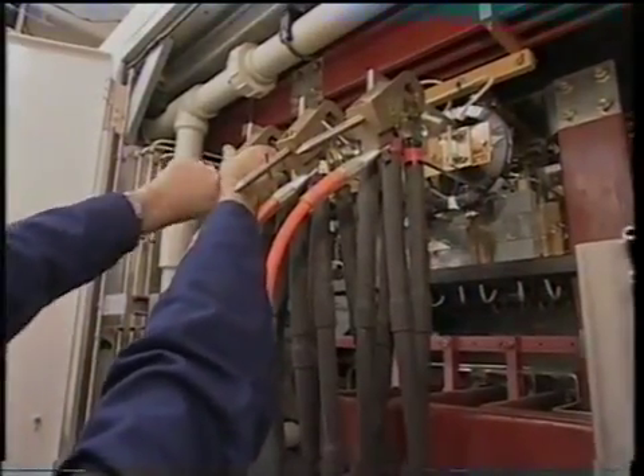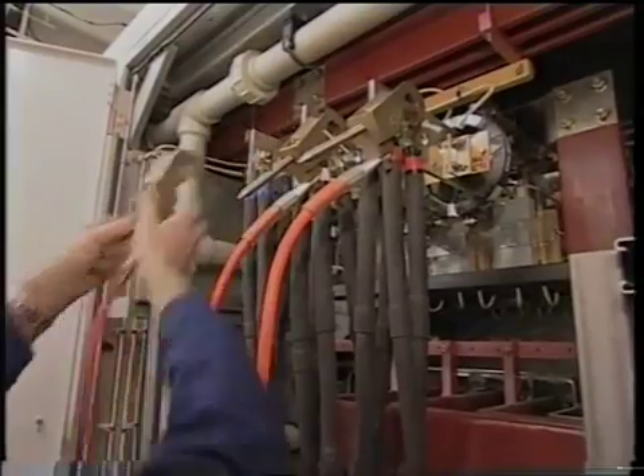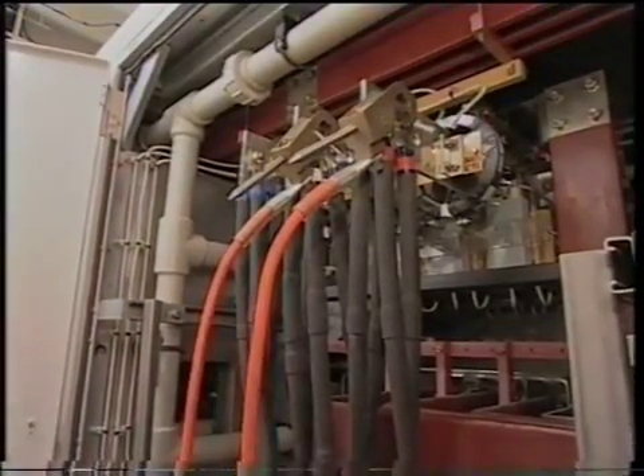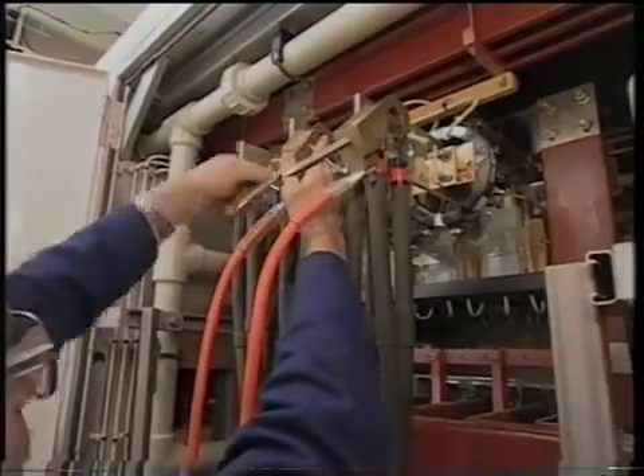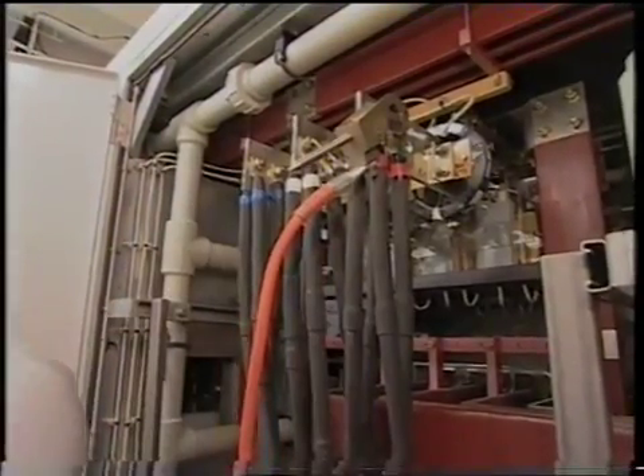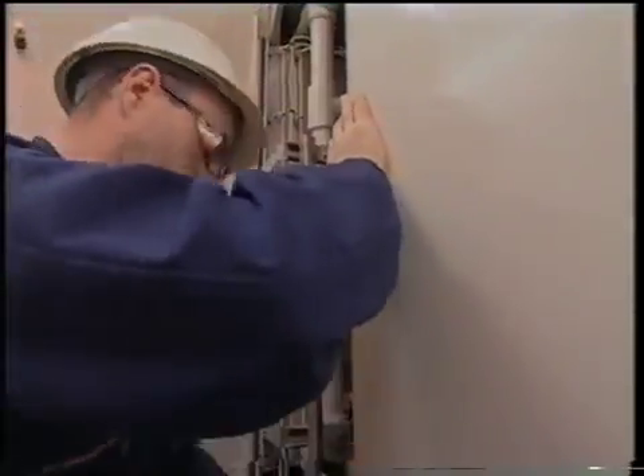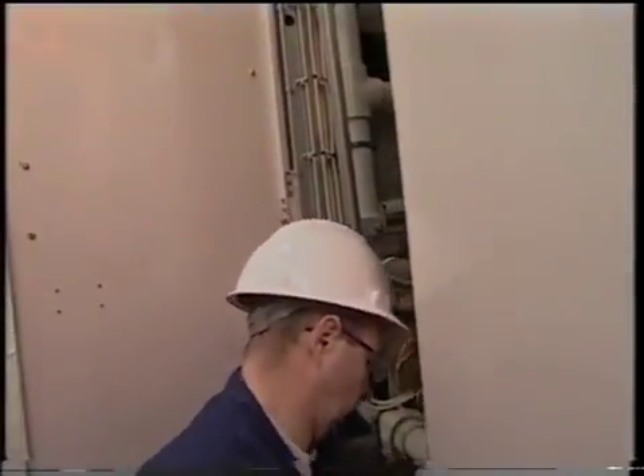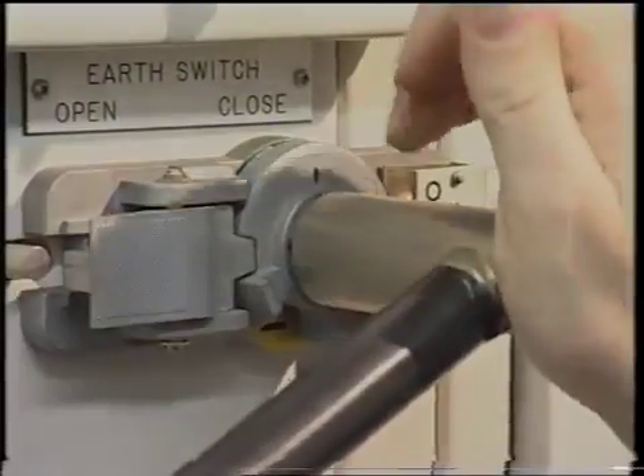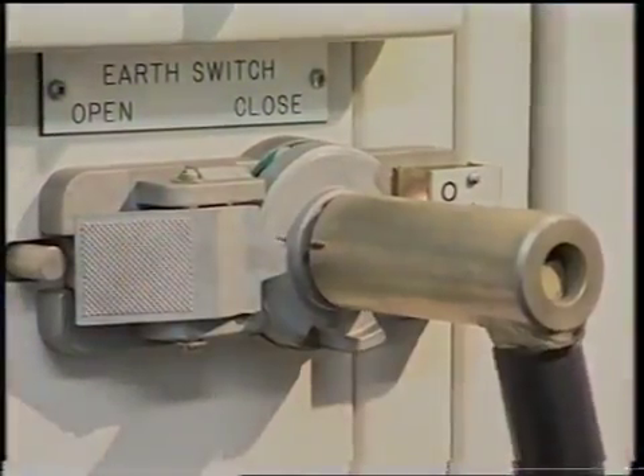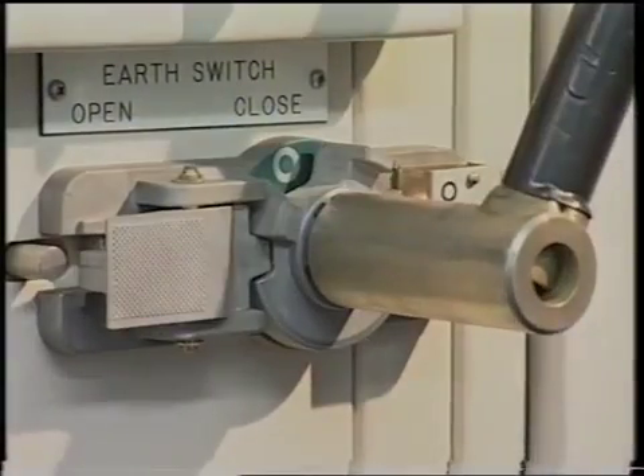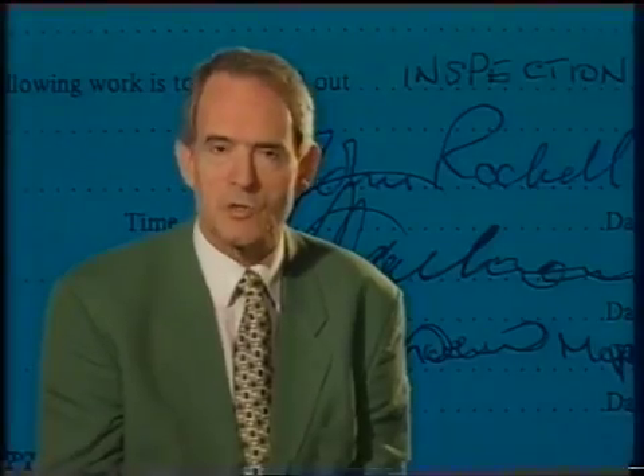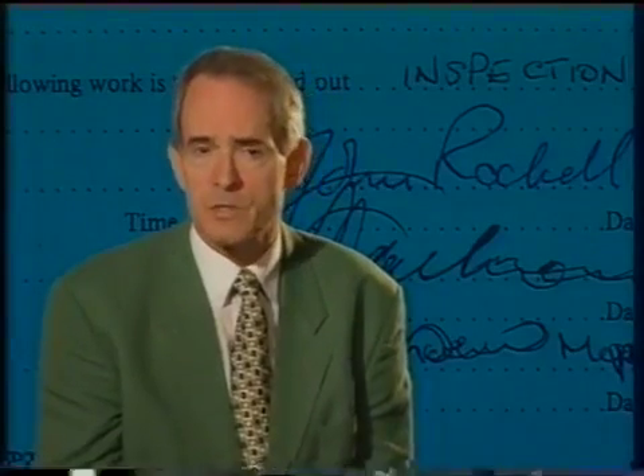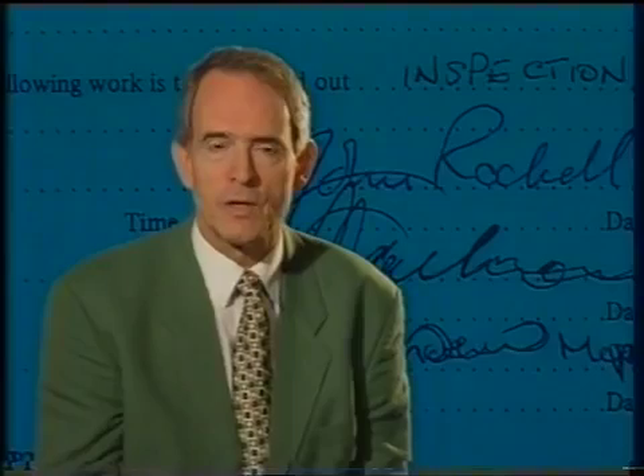After all tests and other maintenance tasks are completed, as listed on the permit to work, the additional earth leads are removed, first from the phases and then from the local earth point. The panel doors are closed and locked and the warning signs removed. The circuit breaker tags will also be removed and the locks returned to the lockout box. The circuit breaker earth is now disconnected and the circuit is now available for normal service. The sanction to test, isolation certificate and permit to work are now completed, signed off and cancelled.